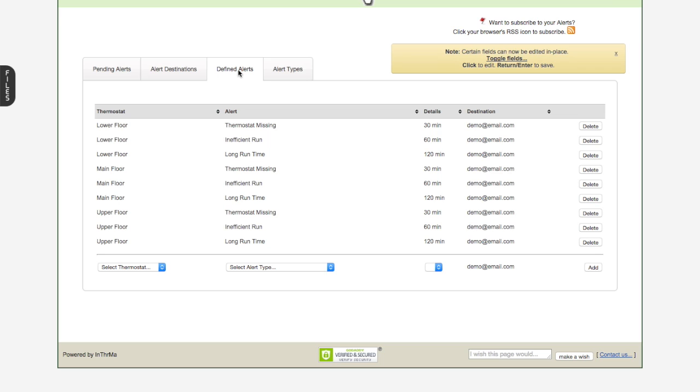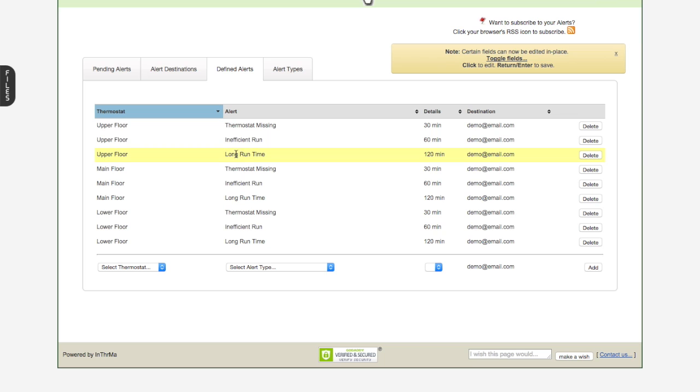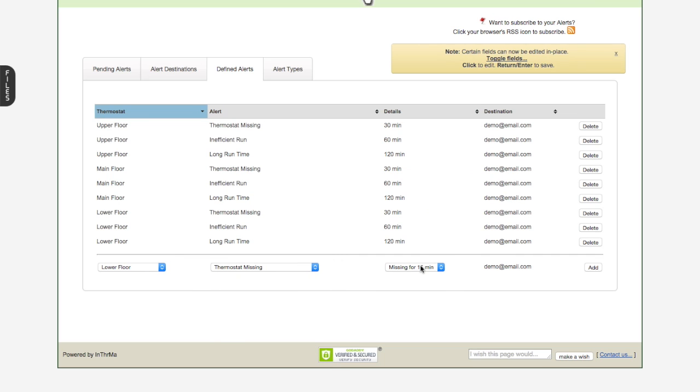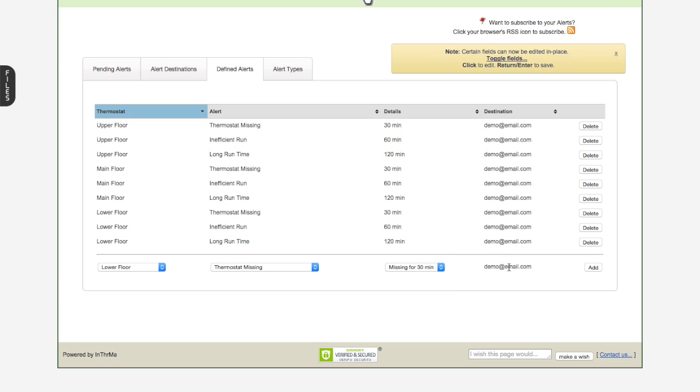So once your destinations are set up, which are email addresses or phone numbers, then you'll come into here. This user, let's do a quick sort by thermostat, they've basically set up three alerts on all their thermostats, the same three. They've set up thermostat missing, inefficient run, and long run time. So thermostat missing is very straightforward. You would select the thermostat, you'd say thermostat missing, and basically select the threshold. So basically, if the thermostat goes off the network for whatever reason, let me know within X number of minutes. So it's a threshold that you'll pick here. And if you have more than one destination, you would pick it here, and you'd hit add. So that's the thermostat missing, very straightforward.